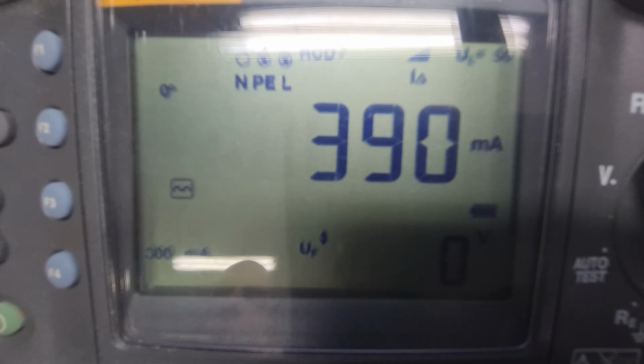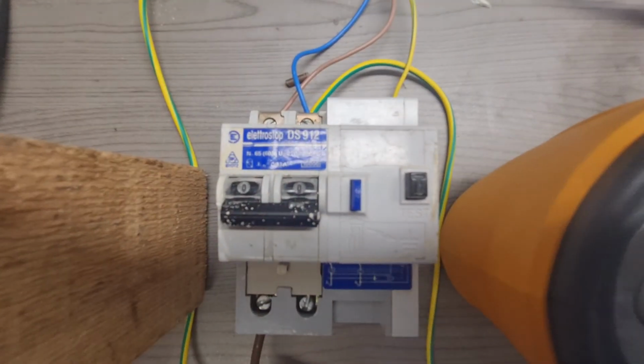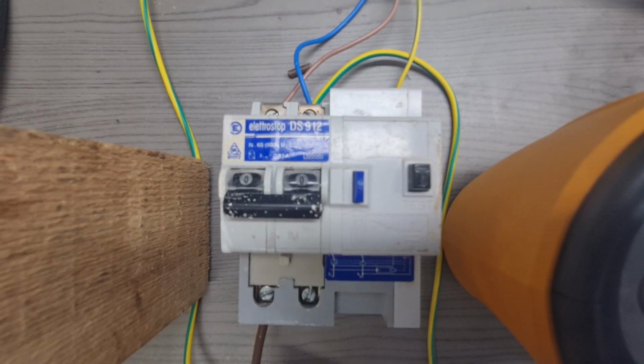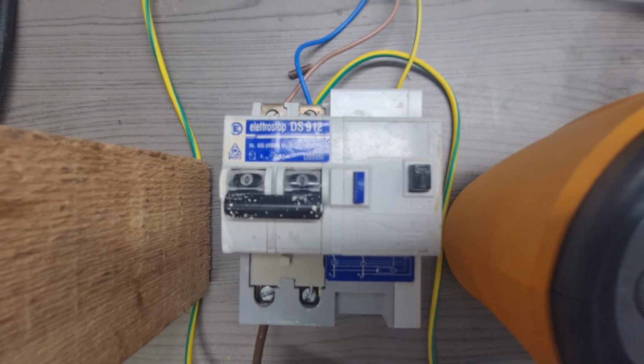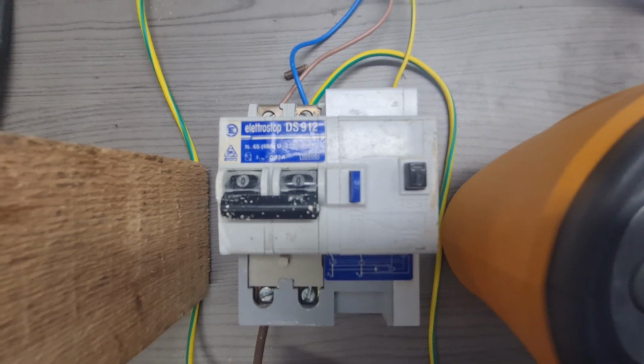Obviously, if we had to test, as we have done in previous videos, a 30 milliamp RCD with DC ripple, it would trip at a current which is less than the 30 milliamps, as opposed to what we have seen here. So check your consumer units, especially if you live in old properties, and if you have something which is similar to this Elettrostop, or even if it is a slightly more modern RCD, it is highly recommended to change it, because the cost of the RCD is a few tens of euros, which is nothing compared to the safety benefits of such a device.